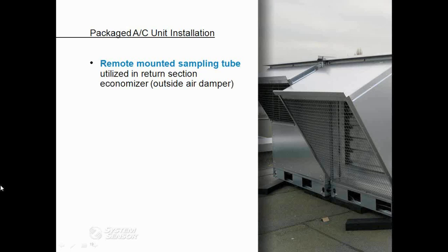In order to utilize remote sampling, this is where it's particularly important to use differential pressure testing to ensure that proper air is going to be sampled, since you do have that additional flexible tubing that the air needs to circulate through.